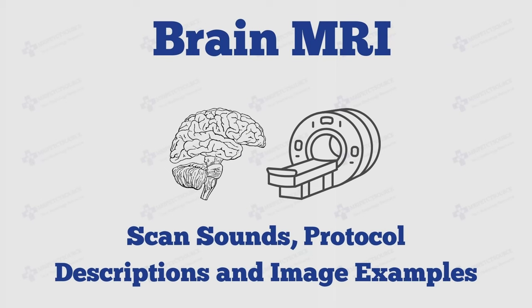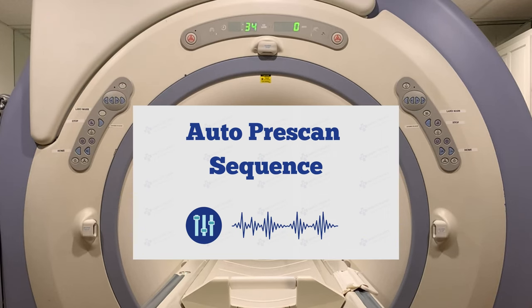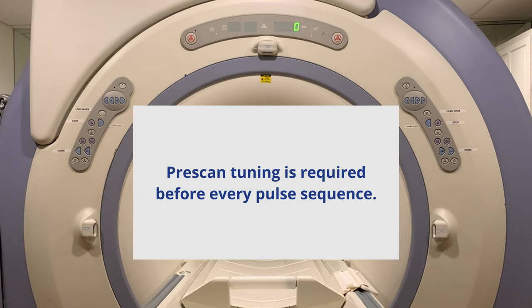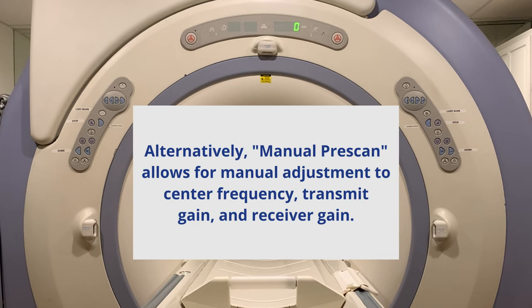Now let's get started with the first pulse sequence you hear during a brain MRI scan, the auto pre-scan tuning sequence. Auto pre-scan tuning is performed prior to each scan series to determine optimal center frequency, RF output, and offset values. Images are not produced during the pre-scan tuning phase.